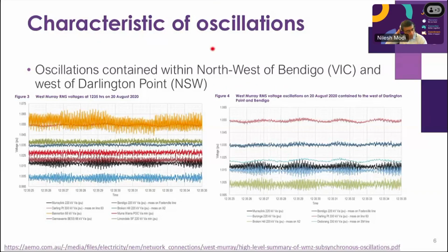When we started looking at the characteristics of the oscillation, there were some consistent observations. The first one was that these oscillations were contained within northwest of Bendigo and west of Darlington Point, which is basically saying it was contained in the West Murray area. As we move away from that area, the presence of this oscillation was not noticeable in the high resolution measurements. These are two snapshots of two events. There were a number of events we have observed, but this is just an example to show how it looked in a high resolution measurement.